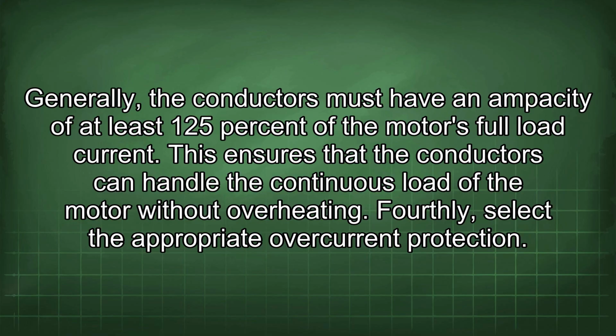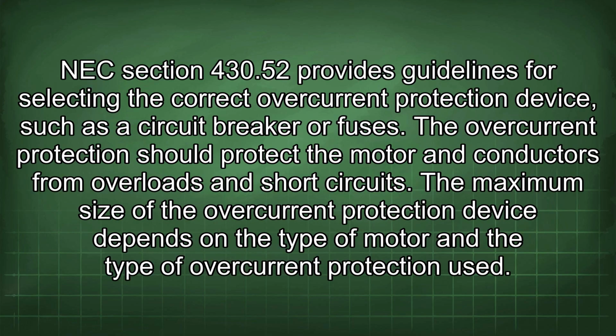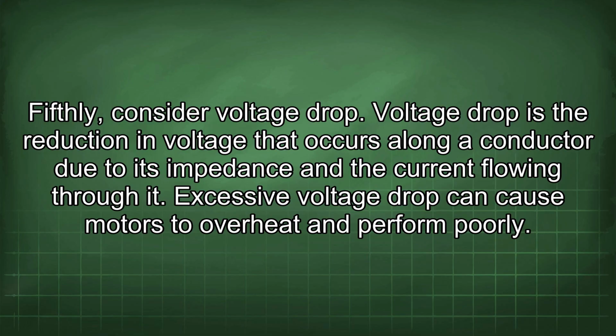Fourthly, select the appropriate overcurrent protection. NEC Section 430.52 provides guidelines for selecting the correct overcurrent protection device, such as a circuit breaker or fuses. The overcurrent protection should protect the motor and conductors from overloads and short circuits. The maximum size of the overcurrent protection device depends on the type of motor and the type of overcurrent protection used. Fifthly, consider voltage drop.